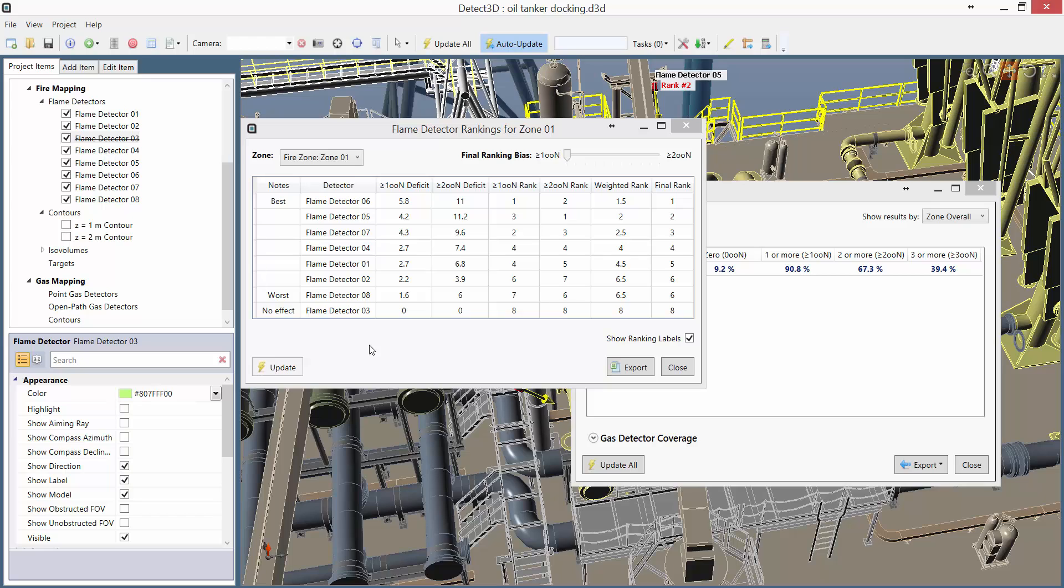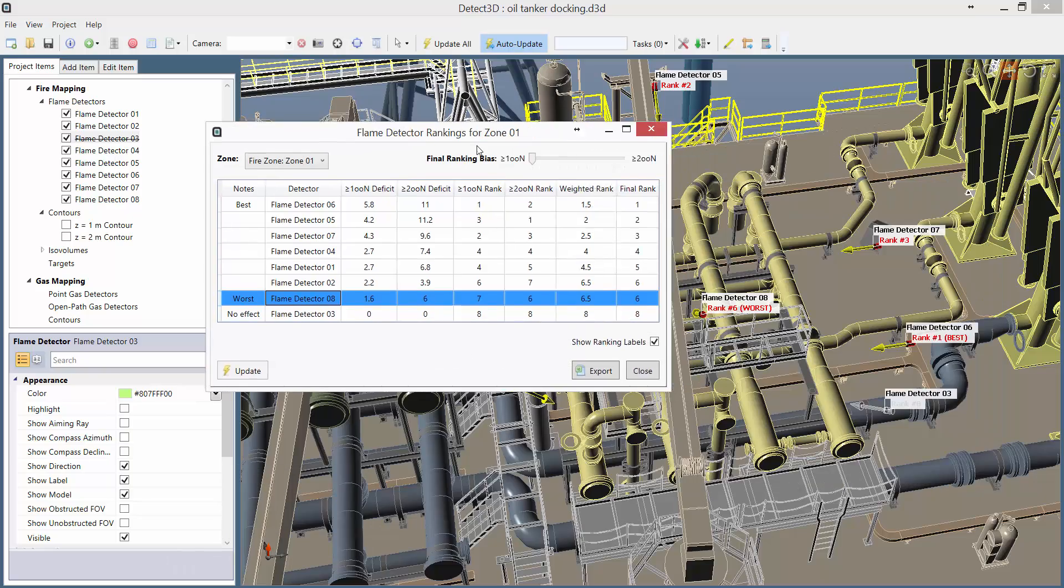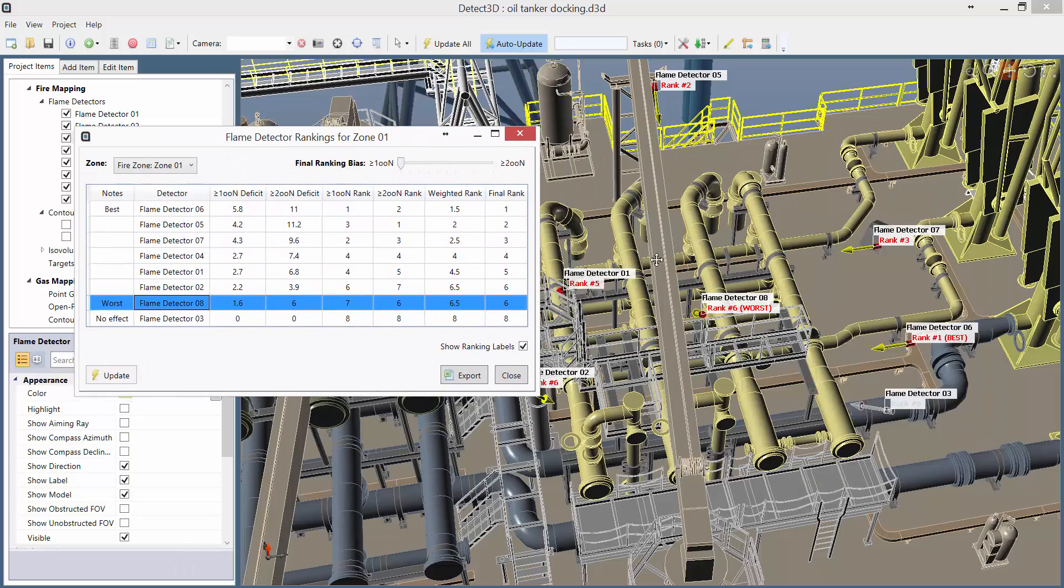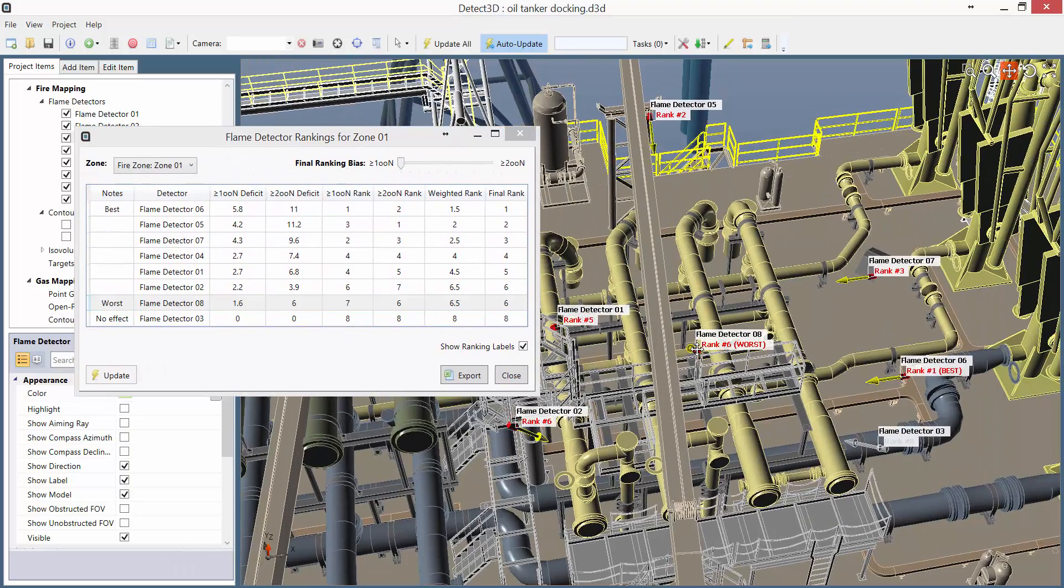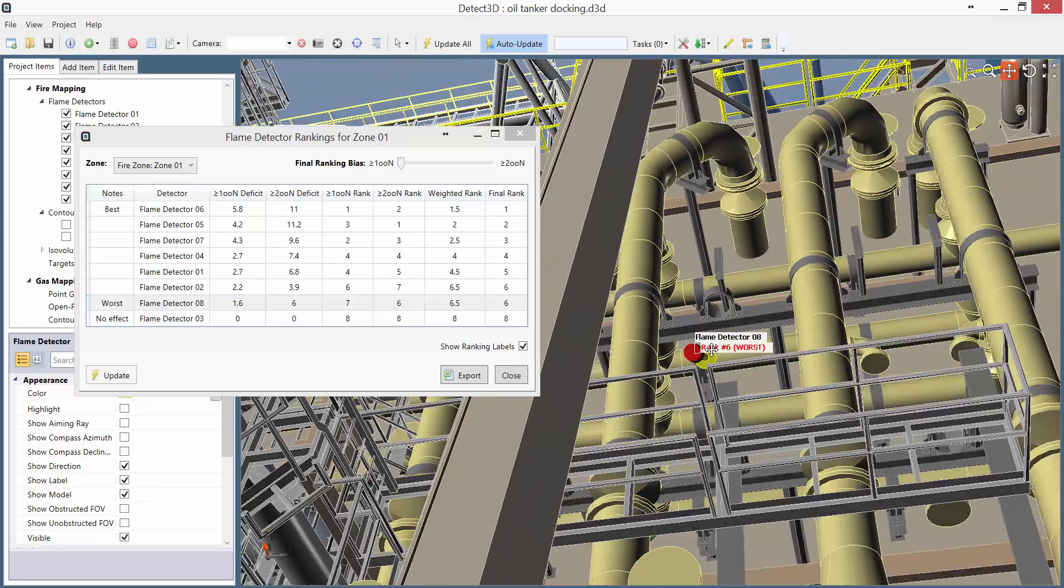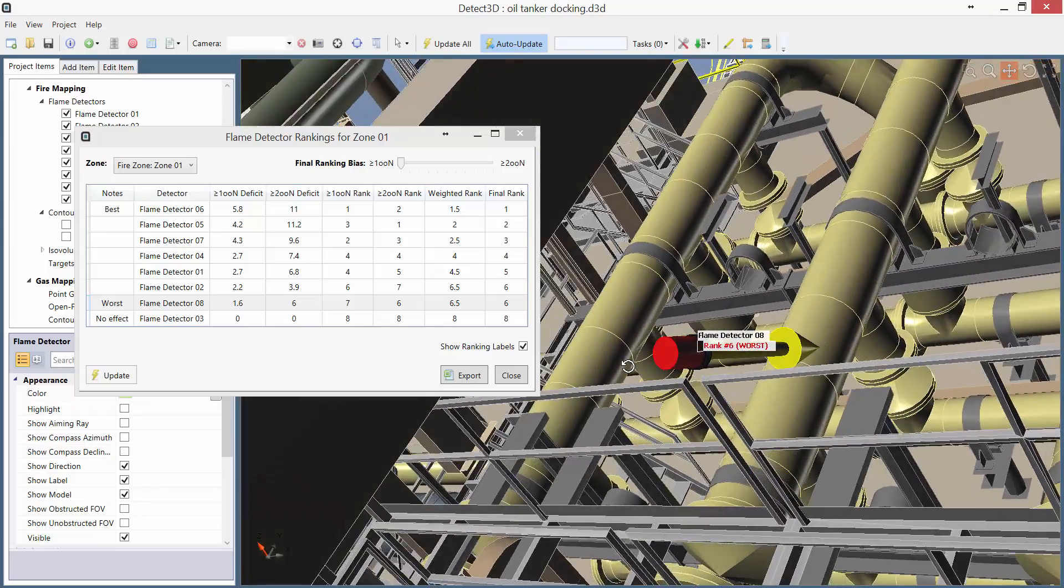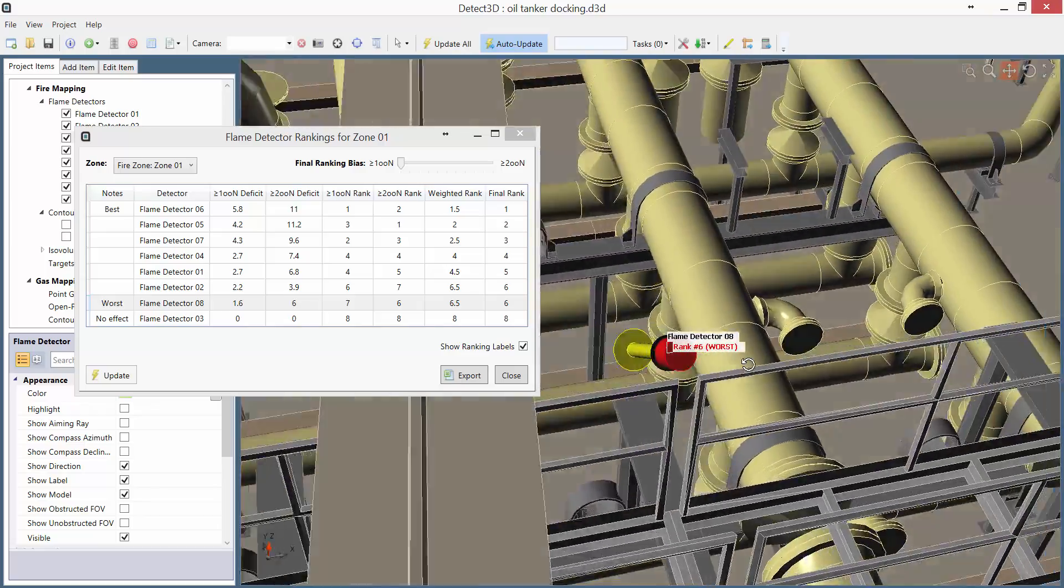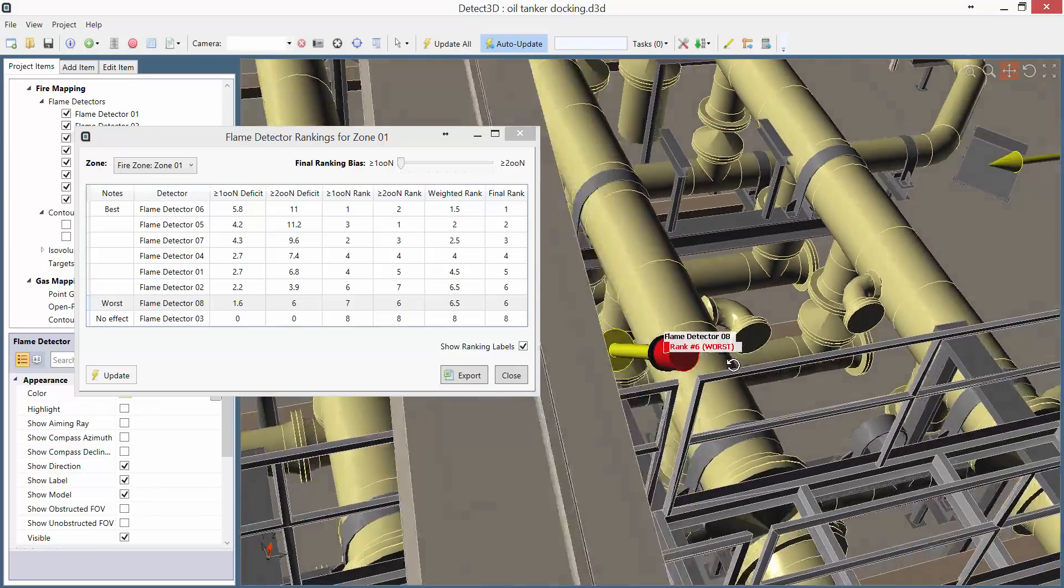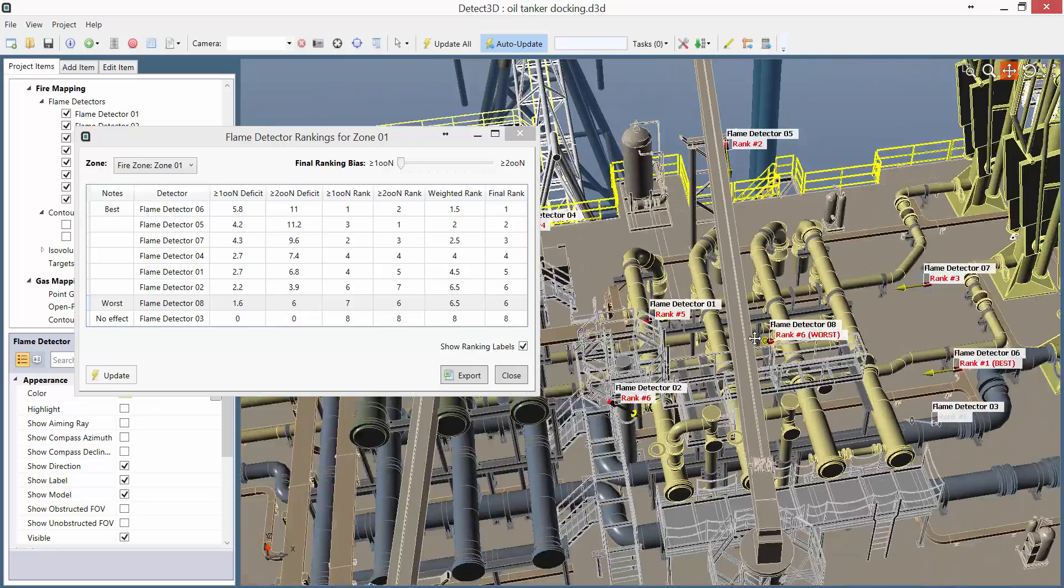I've now updated the detector ranking results, and we can see now that our worst positioned detector is Flame Detector 08. If we take a quick look at Detector 8 in the main window, it may be surprising that it's the worst place, because it's right in the middle of the zone, but we can see it's pretty well obstructed by some large pipe work either side.